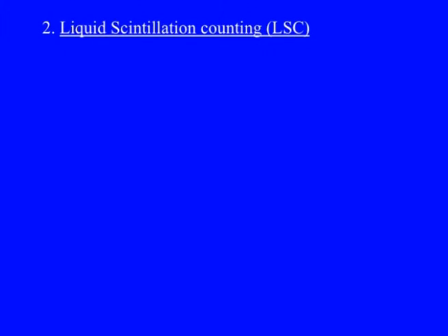In this lecture, we are going to start with another scintillation counting method, which is the most widely used, that is the liquid scintillation counting method. Now, GM counters and solid scintillation counters are inefficient for low energy particles, particularly for 3H, which is widely used in different biotechnological applications. Two major factors limiting their efficiency are that not all emitted particles reach the detector, and not all of those that reach the detector are counted.